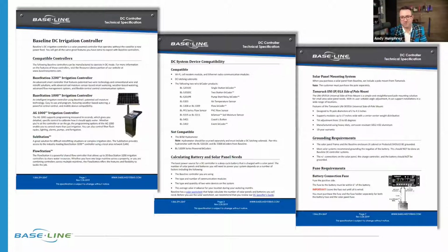No, it's simpler, Chris isn't trying to stump you. He's trying to bring out what we're working with here, which is it's a DC powered system. So the consideration to remember when you order your valves from suppliers is that they will need DC latching solenoids, which seems elementary but can be forgotten. That's the main difference, they're latching. There's not constant power, they latch on, they latch off. You can switch out solenoids, or order your valves with DC solenoids depending on the manufacturer where you get them.